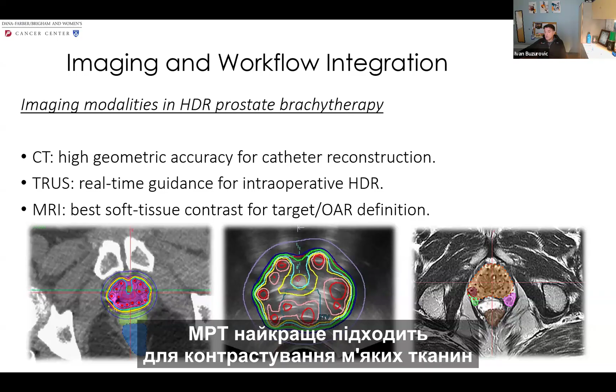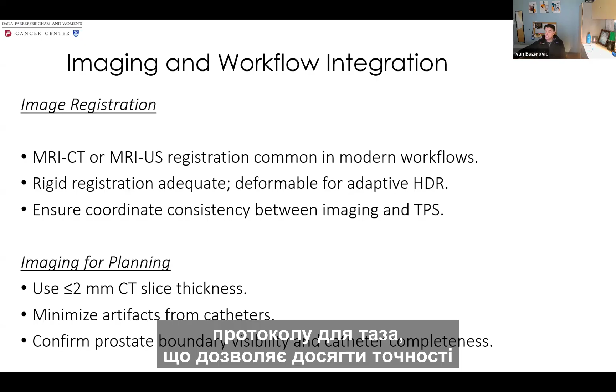Just to remind ourselves that the registration is a procedure in which two or multiple imaging sets are placed into the same coordinate system. So when we use imaging for treatment planning, for instance, for a CT, we should use slice thickness less than 2 millimeters. Usually, the rule of thumb would be half of a standard pelvis protocol for visualization of the catheters, and to allow the accuracy of a source placement of 1 millimeter.